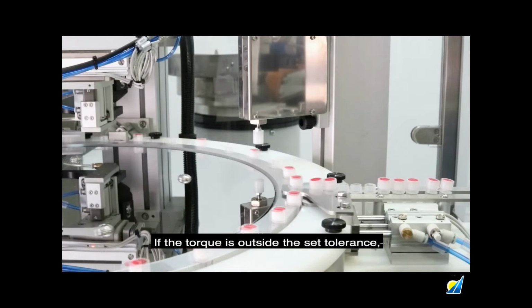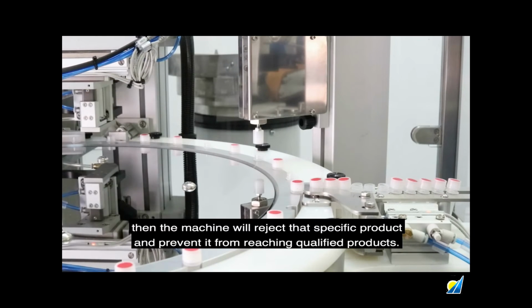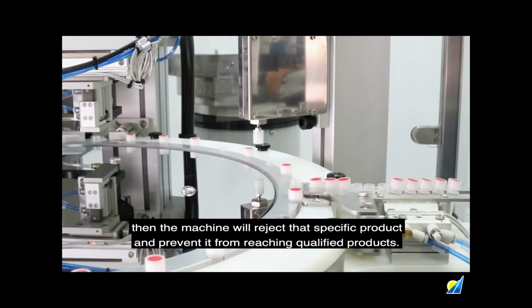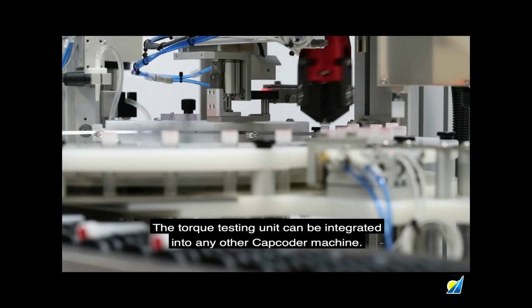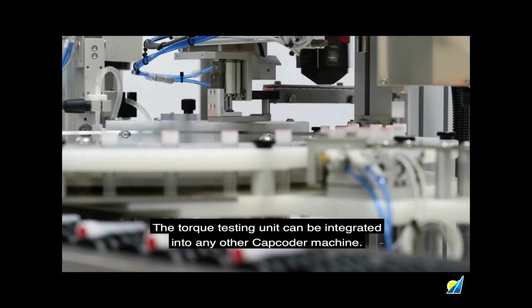If the torque is outside of the set tolerance, then the machine will reject that specific product and prevent it from reaching qualified products. The torque testing unit can be integrated into any other CapCoder machine.